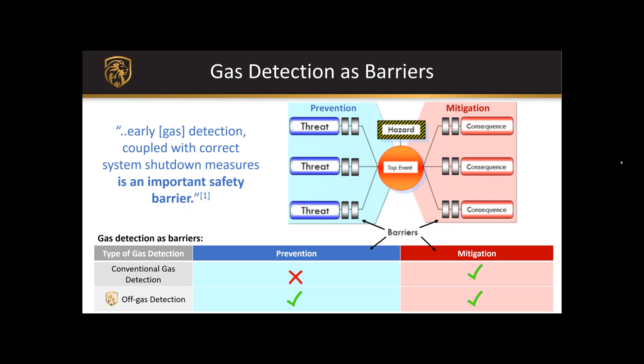At the same time, Li-ion Tamer can also be used to continue monitoring a cell if it goes into thermal runaway. If there's irreparable mechanical damage to a cell and nothing can prevent it from entering thermal runaway, the system can still tell you where the gas has spread, where it's recovering back to pre-incident levels, and can follow that failure all the way through. We'll show some data highlighting that.